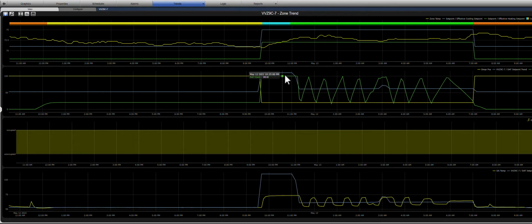And then it went to minimum air, but maximum heating coil to bring it into the space, okay? So this area right here is where we spend our energy, right? Right there, getting it to the set point as quickly as we can. How long did it take? Probably took, this is fighting me a little bit here, 9:40 to about 10:40, something like that.